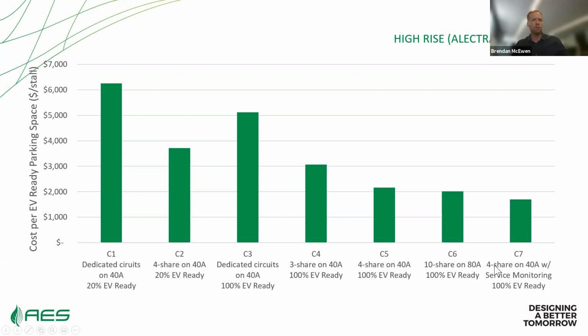C7 here shows 4-share on 40 amp branch circuits using service monitoring. You're designing for service monitoring to be installed and avoid capital upgrades to your utility service and the building's transformer. For the high rise, that was costing around $1,700 per EV-ready parking space.